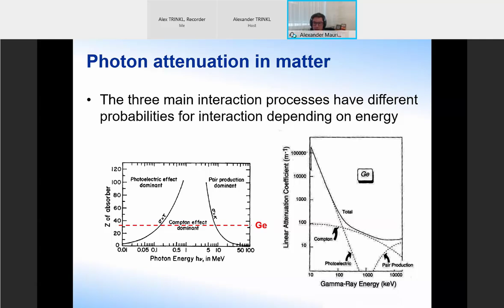There are also some other effects that may contribute. There can be interactions happening not in the detector, but in the materials around the detector, where the leftover radiation is then sent back towards the detector. That's when you'll have such things as backscatter and annihilation photons and so on. There are also summing effects, which we will not go into detail on here, such as true coincidence summing and random summing, basically when more than one photon interacts with the detector in such a short time that the detector interprets it as just one big signal. This can pile up at the higher end of the spectrum or create other effects. There are also peaks that are not related to gamma rays, but rather to X-rays.